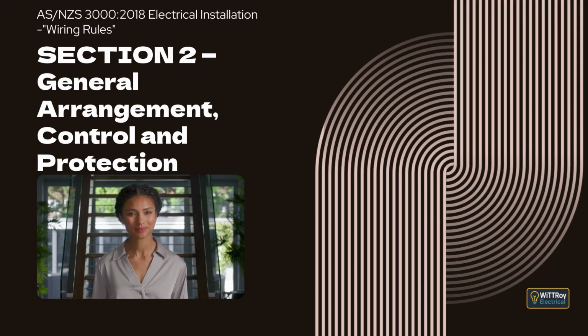This clause explains how to select suitable protective devices and where they must be installed so the installation remains safe. Clause 2.5.4.1, determining the prospective short-circuit current, explains that the prospective short-circuit current must be known at every relevant point in the installation. This value represents the highest fault current that could flow if a short circuit occurred at that location. The value can be obtained either by measurement using suitable test equipment or by calculation. Whichever method is used, the result must be realistic so that protective devices with adequate breaking capacity can be selected.